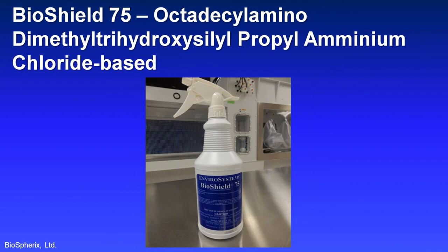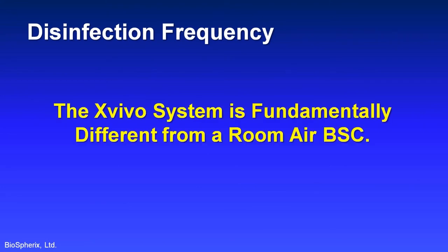Once you choose your appropriate disinfectants, you will decide how often you need to disinfect your systems. But before we go through that topic, I would like to remind you again that the Xvivo system is fundamentally different from a room air BSC, which means no random particles will fall on your surface. HEPA-filtered medical-grade tank gases will significantly reduce the bioburden. Controlled temperature and relative humidity will inhibit microbial growth.